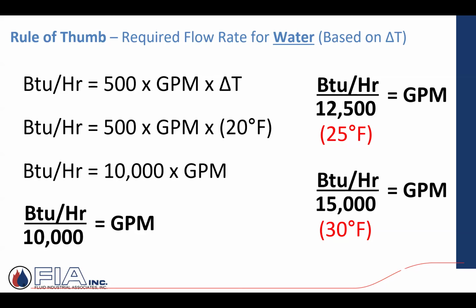It doesn't shock the boiler. Yeah, a question came, if you get the water temperature too low, what does it do to the boiler plant? Depends on the boiler. If I have, say, a stainless steel high efficiency modulating condensing boiler, bring it on. I love it. If you've got a sectional cast iron boiler, like a hot plate, I don't want to run ice cold water under it or over it. I'm going to thermally stress it and eventually shock it and damage that plant.